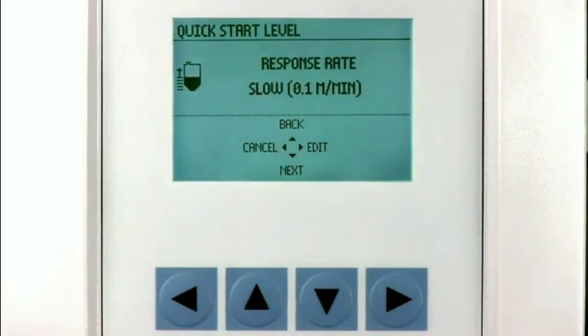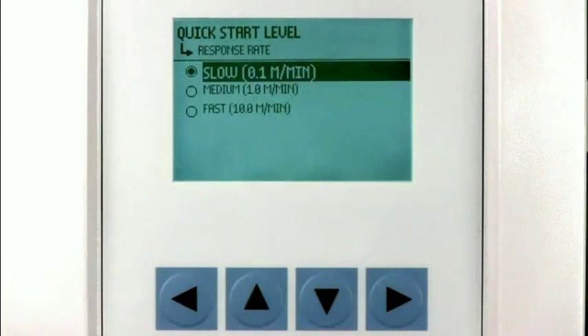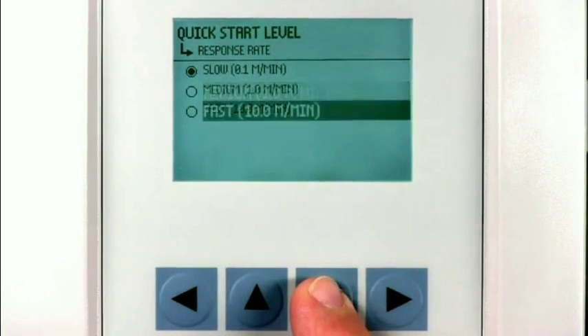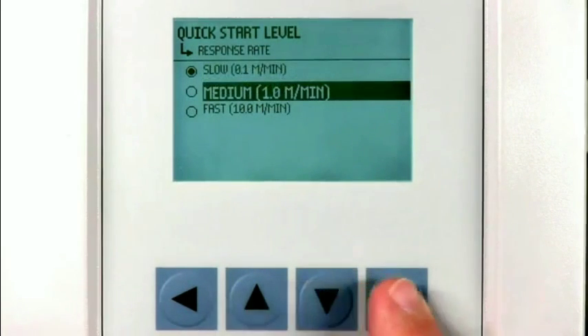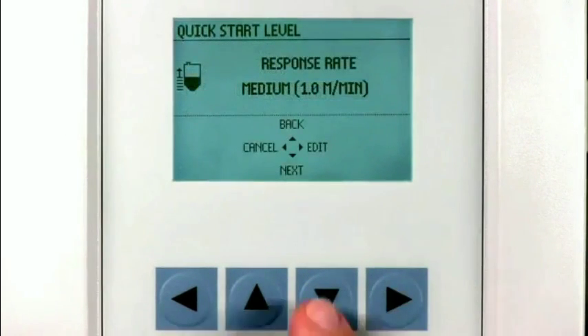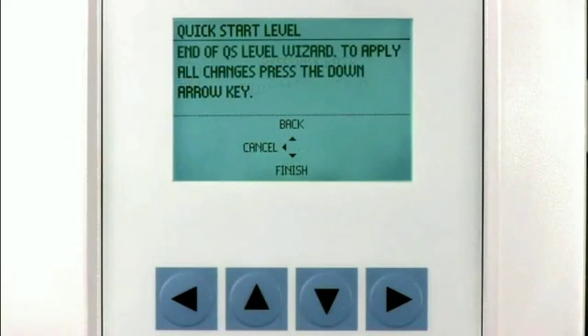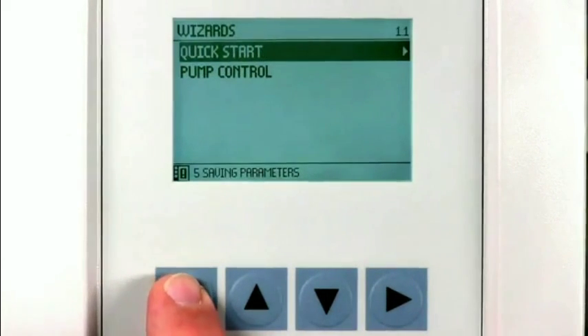The final parameter is the response rate. Set the response rate to a value slightly higher than your maximum process change rate. In our application we will use the medium response rate. Then press the down arrow key again to save all of the settings we just made.